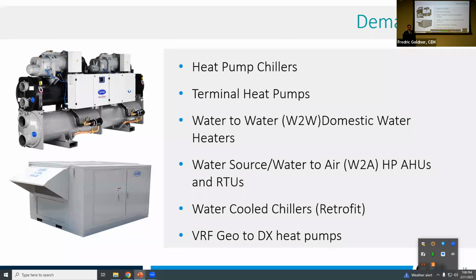Yeah. With the VRF Geo, you potentially have no water anywhere in the system. The refrigerant is literally going underground. No. Okay. So what you've just referred to, sir, is known as DX geothermal or direct exchange. And that's a refrigerant loop. The compressor is pumping it to either the evaporator or condenser coil, depending upon function. And then that same compressor, unfortunately, is forcing that refrigerant all the way into the ground and then back up.